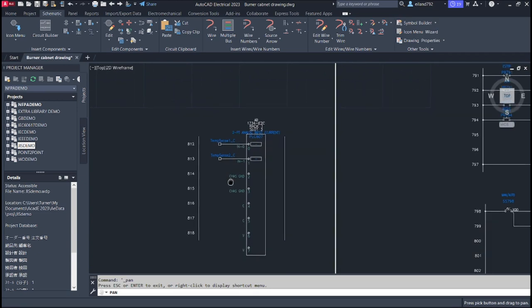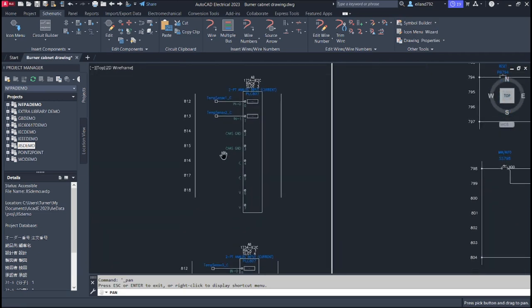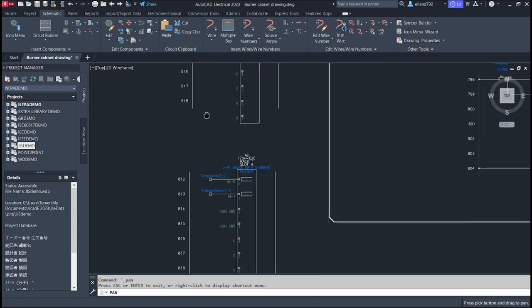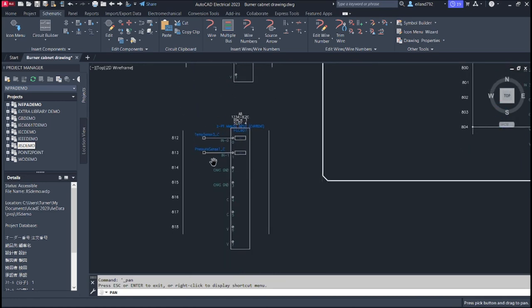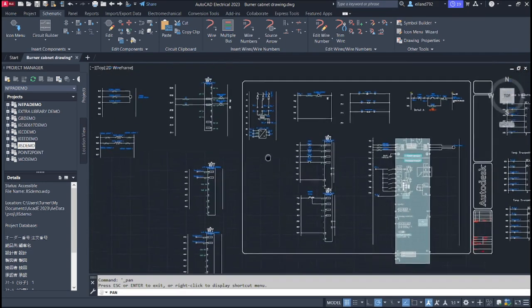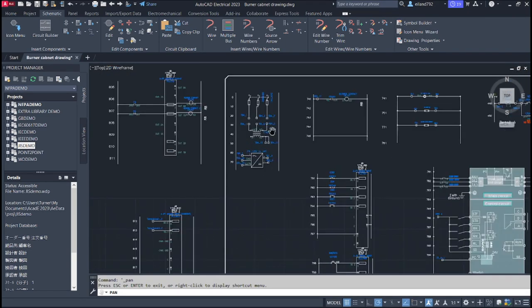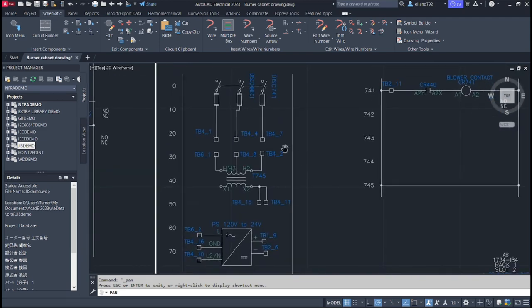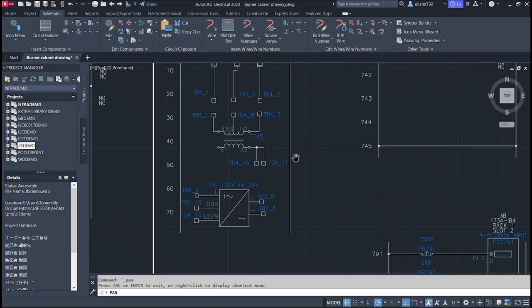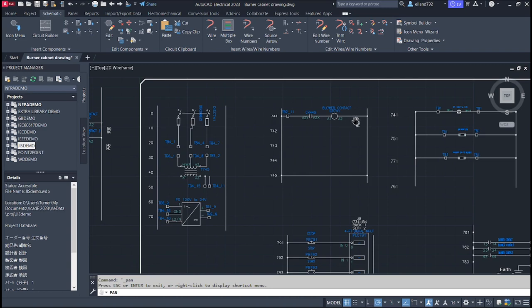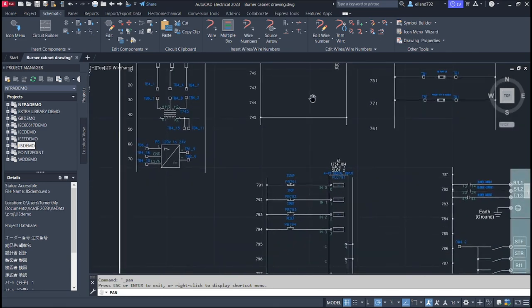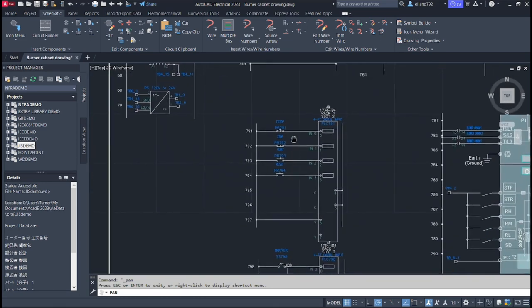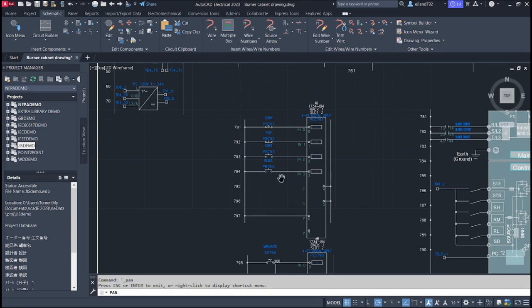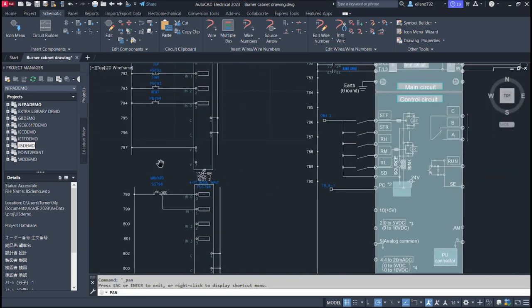Then we have our 4-20 milliamp analog input card for our temp sensors, 2 of our temp sensors, and then the other one is for one of the temp sensors and the one pressure sensor we have. And this right here shows my disconnect and how it goes through the transformer. And then our 24 volt power supply. Here we have our blower contact that's powered from our relay. Our digital input card. This is how we tell whether the e-stop, stop, start, reset's pressed. And then we have our selector switch down here.